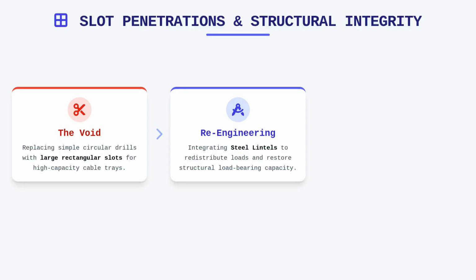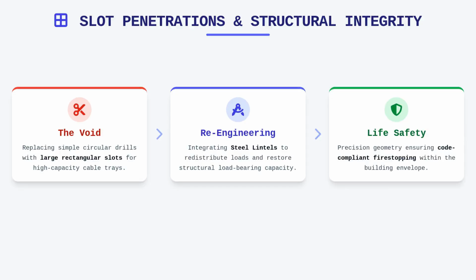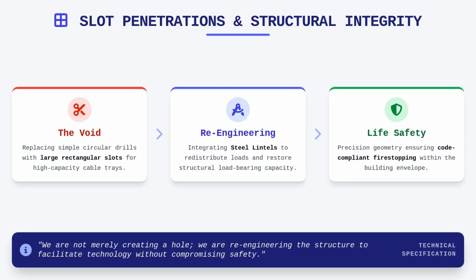The spatial geometry of these slots must be calculated with precision to maintain the continuity of the tray system, while ensuring that there is sufficient room remaining for code-compliant fire-stopping materials. We are not merely creating a hole, we are re-engineering a small section of the building envelope to facilitate technology while protecting the life safety rating of the structure.